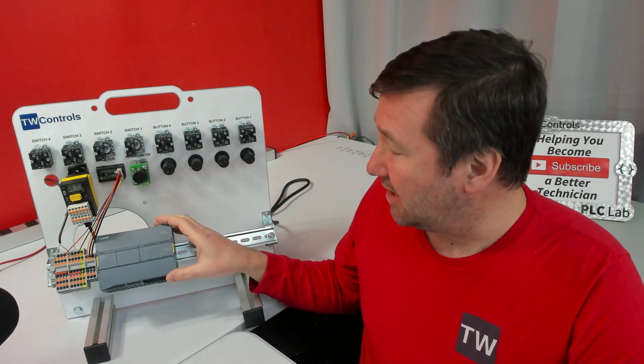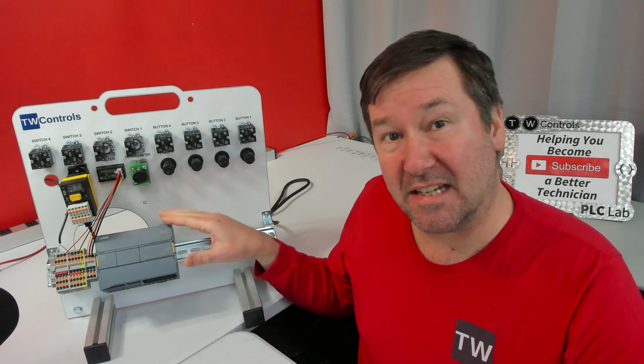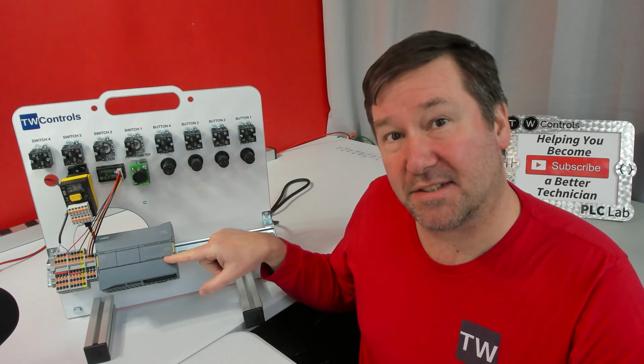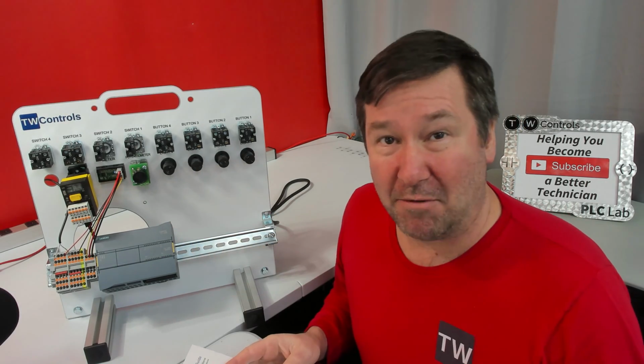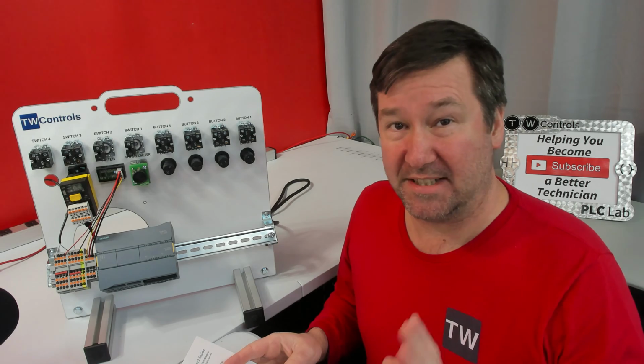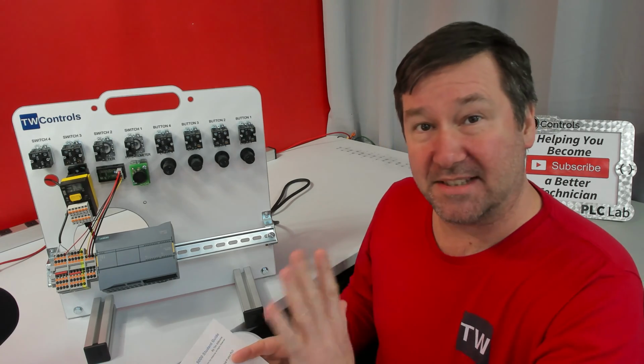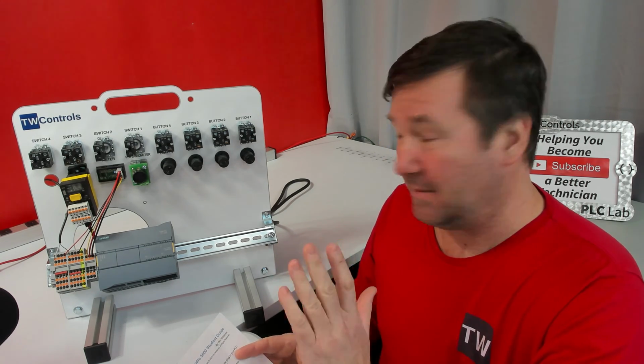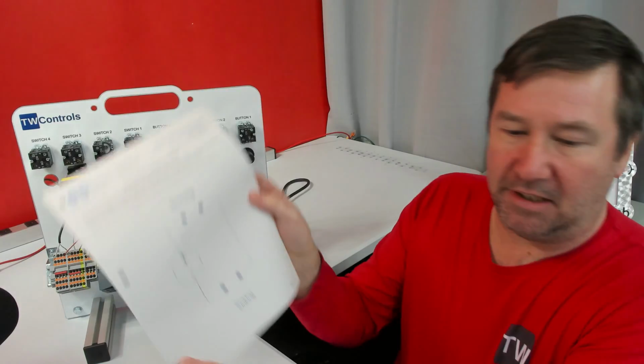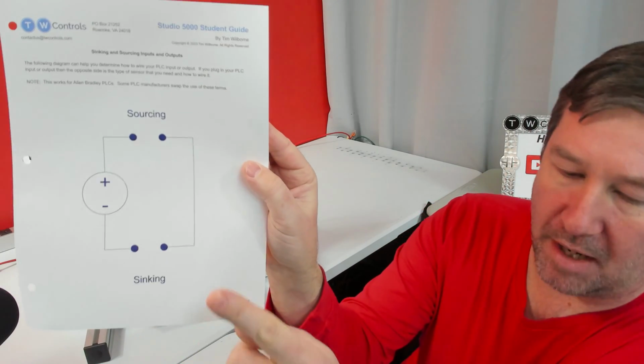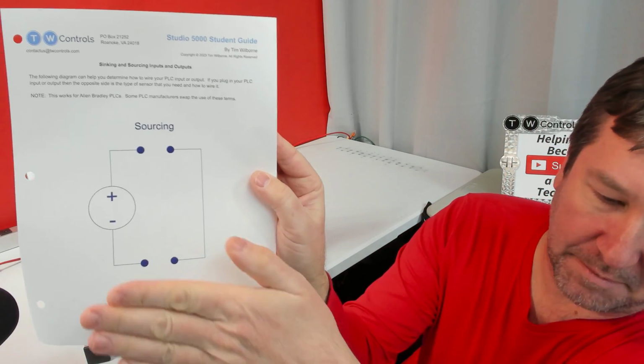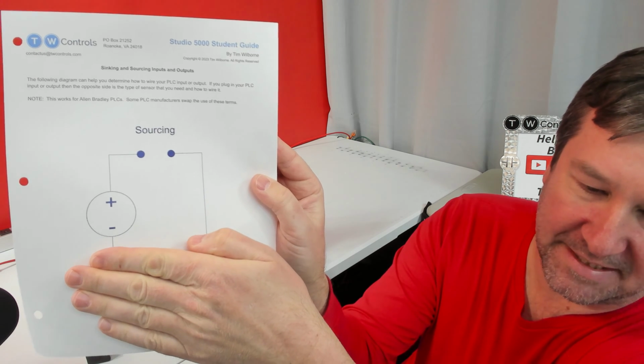This particular S7-1200's inputs can be sinking or sourcing, and it has sourcing outputs. We already have a video on the difference between sinking and sourcing, and the same principles apply to Siemens that we used in it. So if we look at the same diagram, I want to wire my inputs as sinking. So I'm just going to put my hand over that, and that tells me exactly how to wire it.